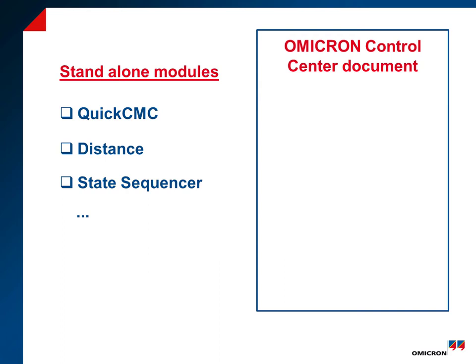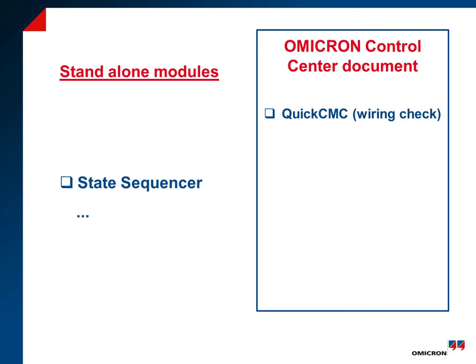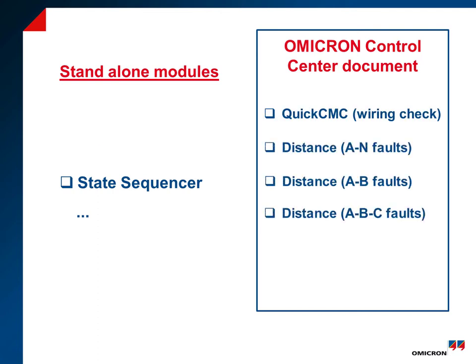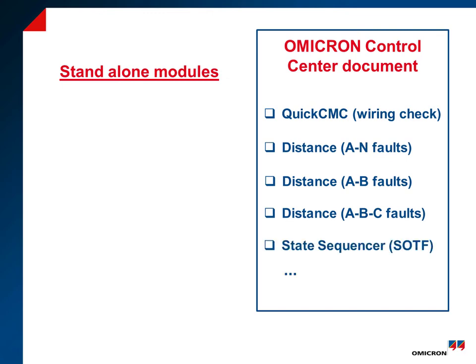For instance, the document can contain a variety of modules, like a quick CMC module for the wiring check, distance modules to check the impedance zones, or state sequencer modules to test the switch-on-to-fault protection function.